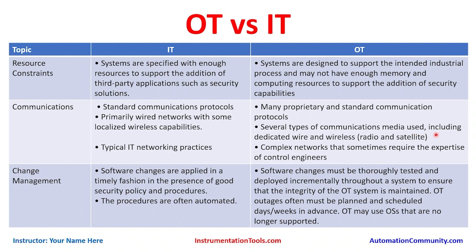Several communication media types are used in OT, including dedicated wired and wireless radio. Not all cable connections are RJ45 — it could be RS232, two-wire, or four-wire communication. For example, an RTD connection could be two-wire, three-wire, or four-wire from field to I/O card. Profibus uses two or three-wire communication; Profinet looks like Ethernet but uses a different protocol. Modbus can run on two-wire, or Modbus TCP can use an Ethernet cable via a converter.